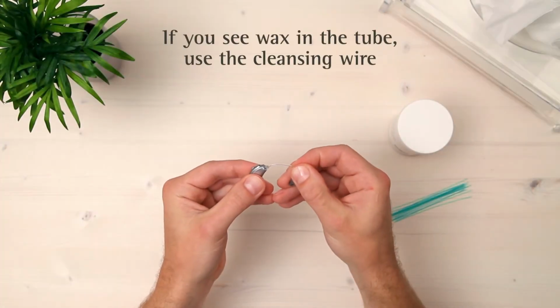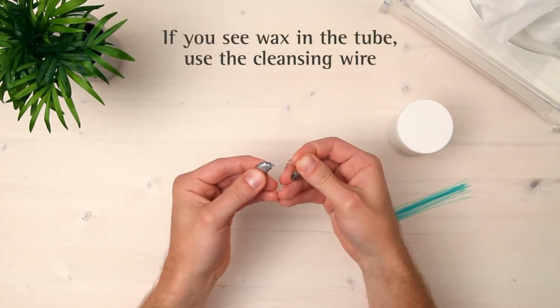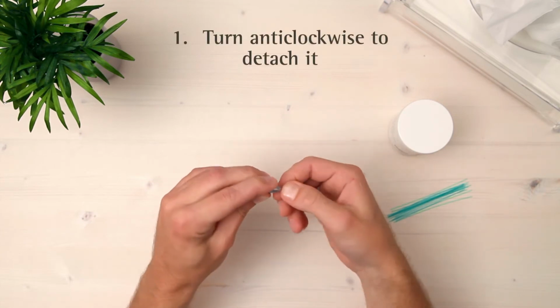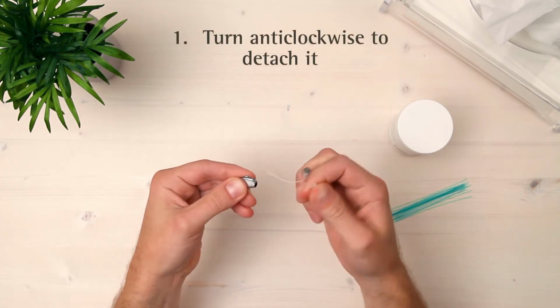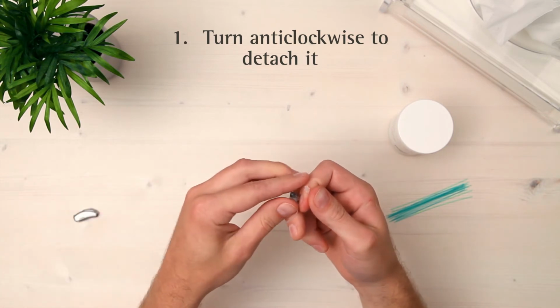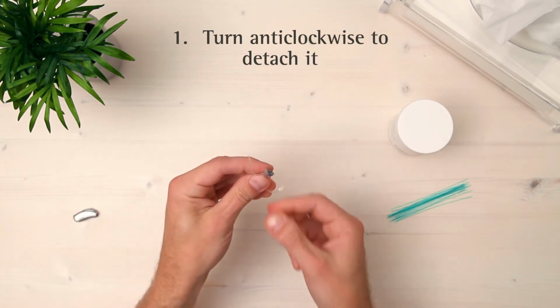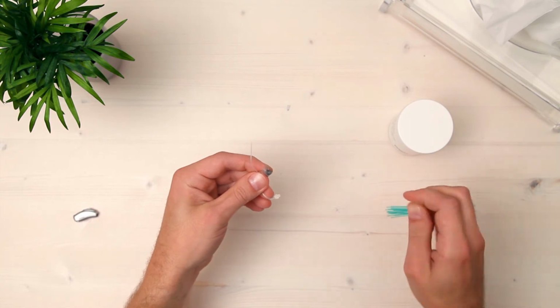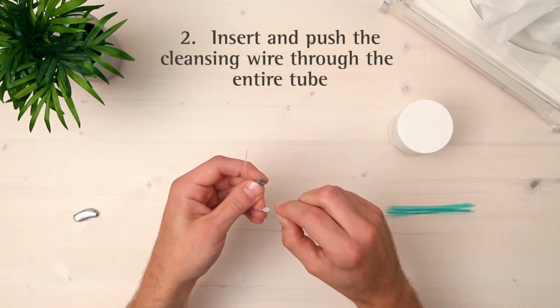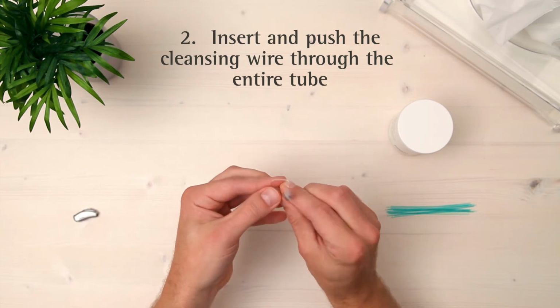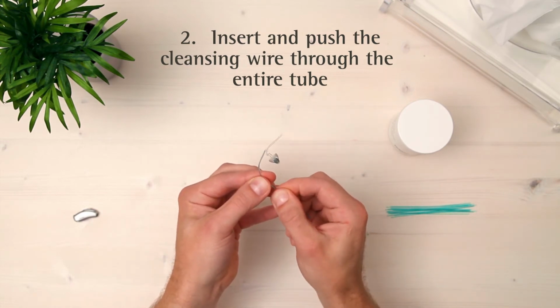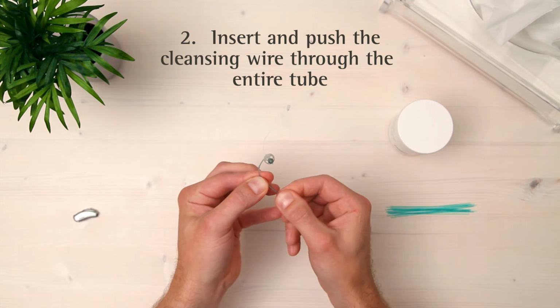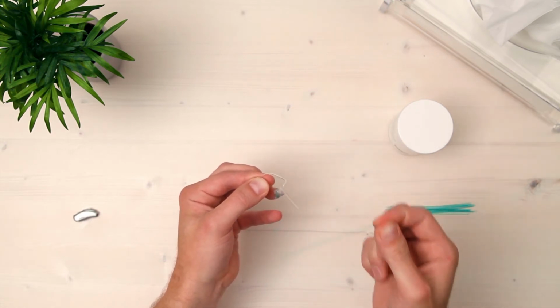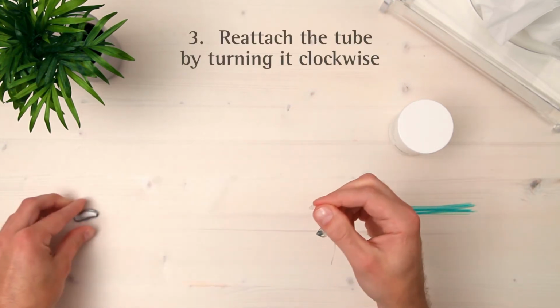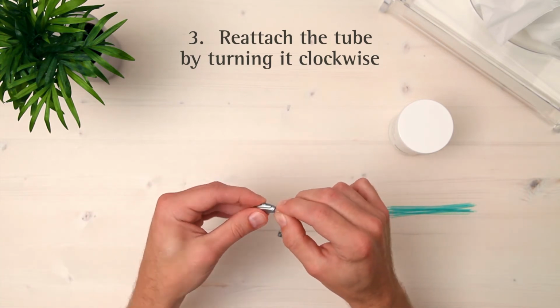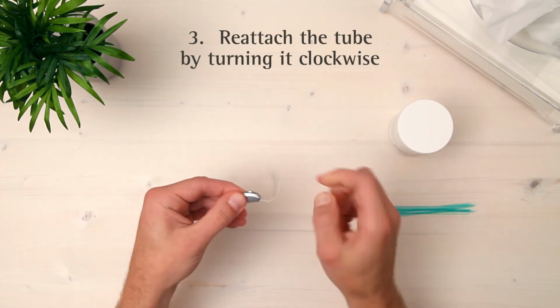Check the inside of the tube for wax or dirt. You can remove this using a cleaning wire. Turn the tube anti-clockwise to detach it from the hearing aid. Insert the cleaning wire and push it through the entire length of the tube. When finished, reattach the tube to the hearing aid by turning the tube clockwise.